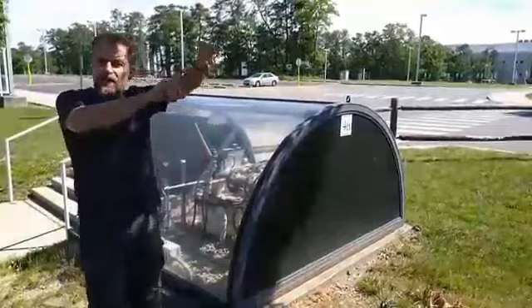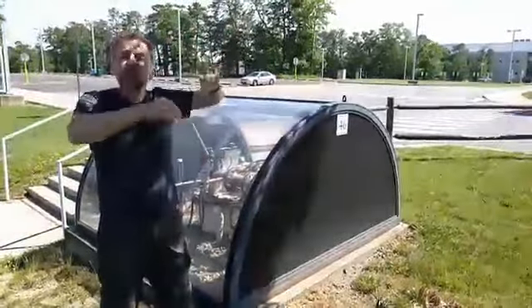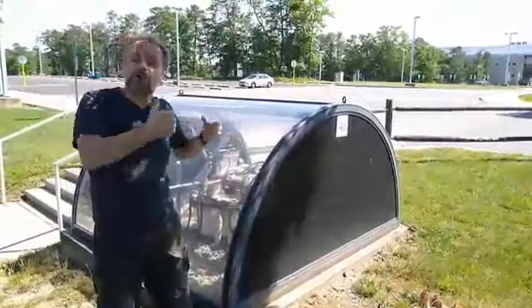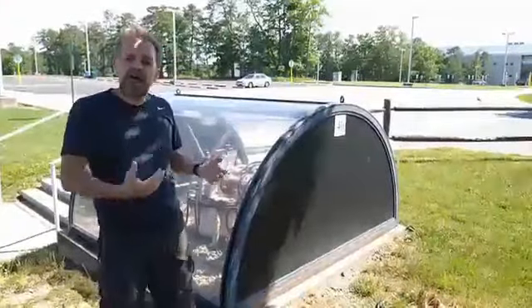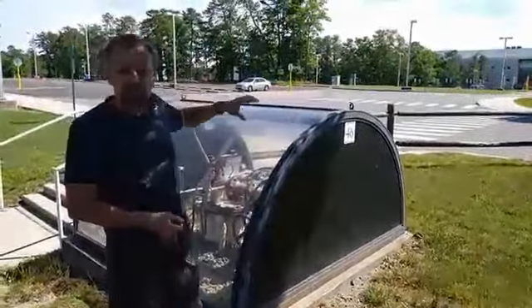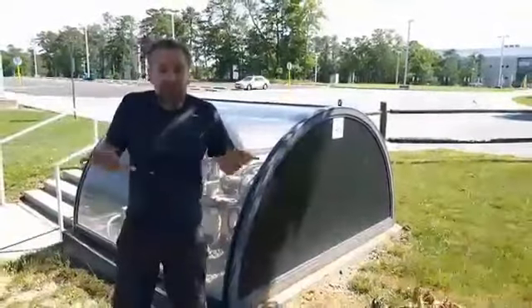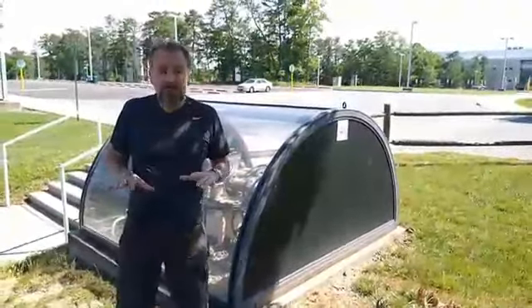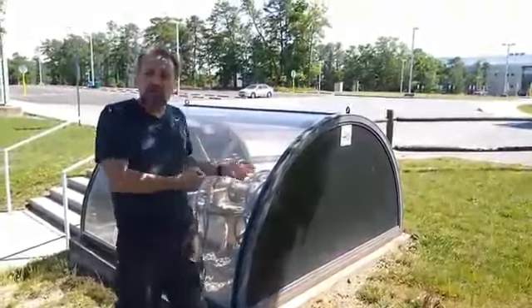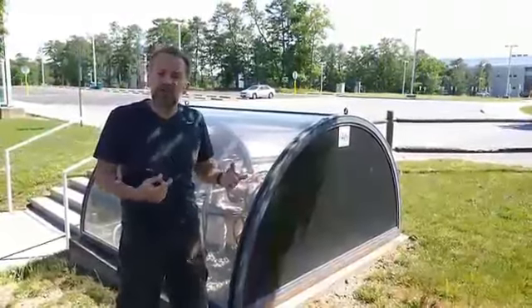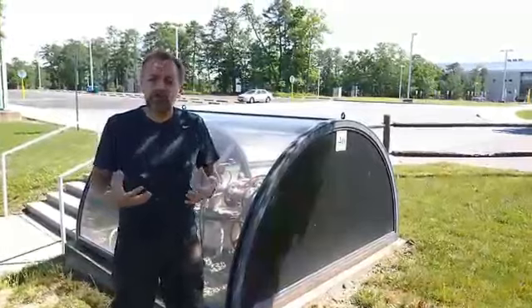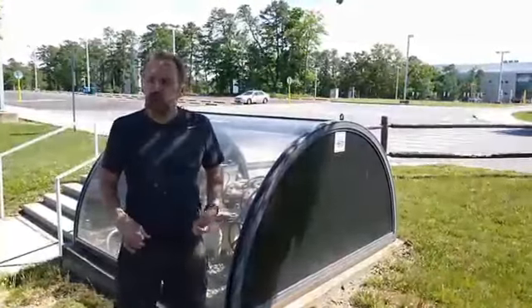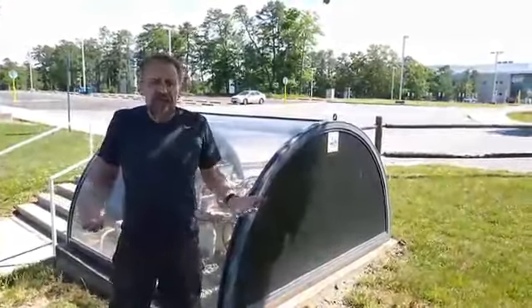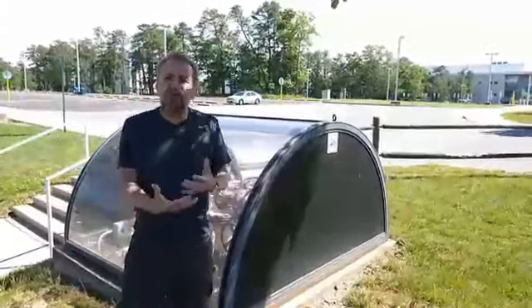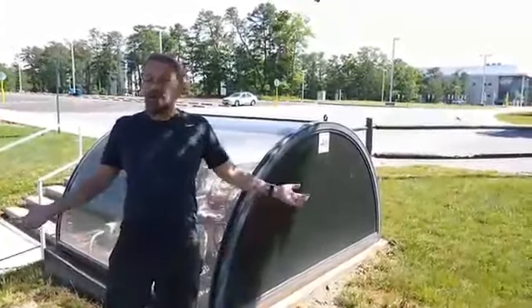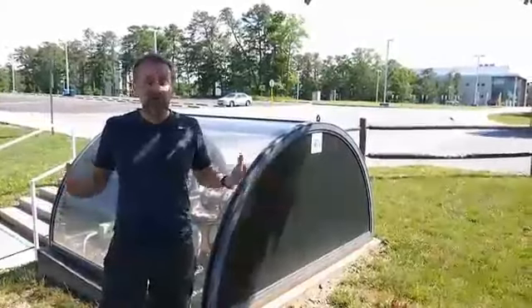So imagine another radiator on the roof where we have those heat pumps to pre-cool the air before it goes into the geothermal system. So now we not only have a geothermal system which provides a stable, roughly 60 degree temperature, but we can pre-cool so that in the summers, when we need the air conditioners, we can lighten the load on the geothermal system by dropping the temperature of the incoming air 7, 8, maybe 12 degrees before it comes into the air conditioners. That makes air conditioning a lot easier, and much more efficient.